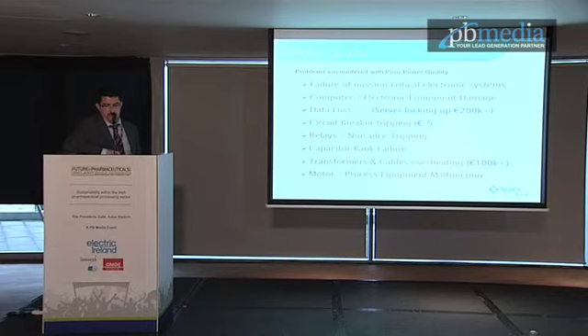Failure of mission-critical electrical systems, computer electronic equipment damage, data loss due to servers locking up, nuisance tripping on circuit breakers, capacitor bank failure, transformers and cables overheating. Just an example there would be here on this one, a neutral cable overheating, because when the infrastructure was originally designed, these were all motive inductive loads. So the neutrals were quite often undersized at the main supplies. Then as energy efficient projects come on stream and more electronic equipment gets added, it's put stress on the neutral.